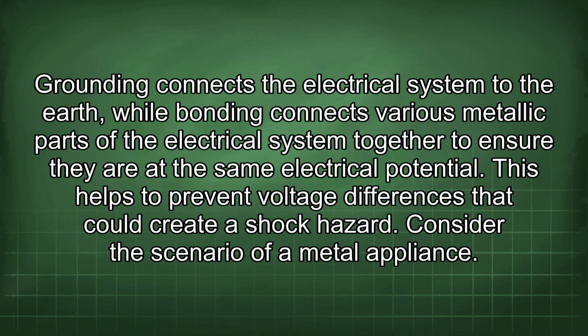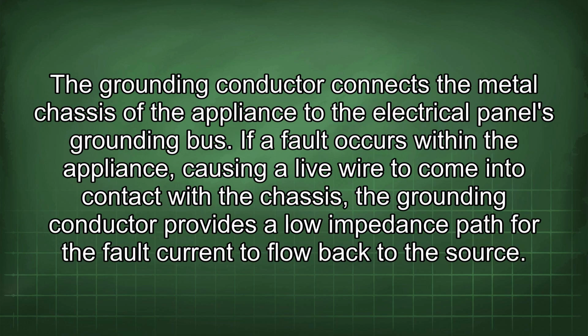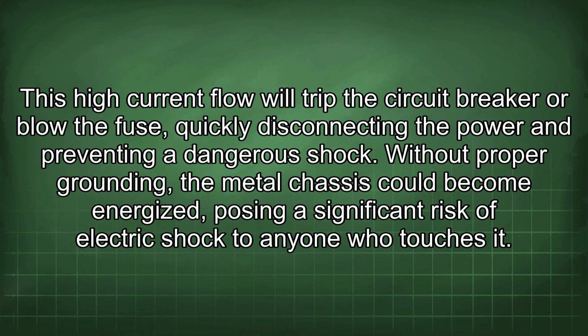Consider the scenario of a metal appliance. The grounding conductor connects the metal chassis of the appliance to the electrical panel's grounding bus. If a fault occurs within the appliance causing a live wire to come into contact with the chassis, the grounding conductor provides a low impedance path for the fault current to flow back to the source. This high current flow will trip the circuit breaker or blow the fuse, quickly disconnecting the power and preventing a dangerous shock. Without proper grounding, the metal chassis could become energized, posing a significant risk of electric shock to anyone who touches it.